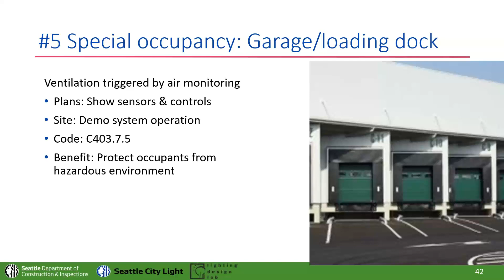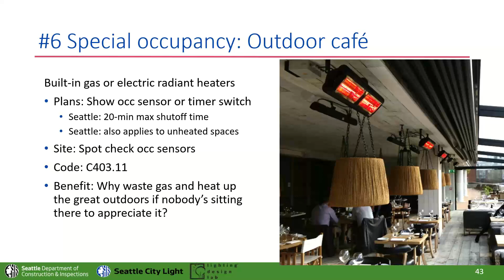We've been seeing a lot of these outdoor cafe setups lately with radiant heaters. In Seattle, you've got to have a 20-minute max shutoff on those, and we also applied it to unheated spaces—so if you have an unheated storage area or equipment shed, say with a bay where someone's working on an engine, you can have one of these heaters as long as it has that shutoff system.